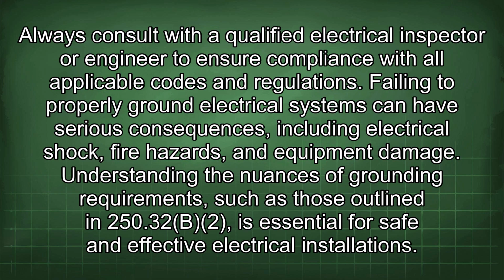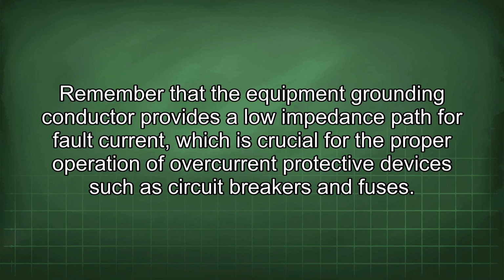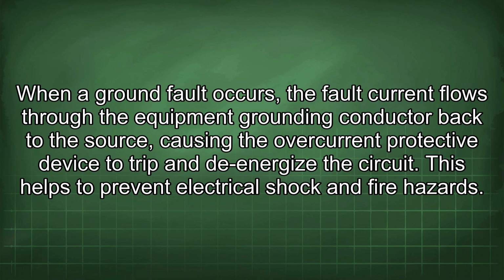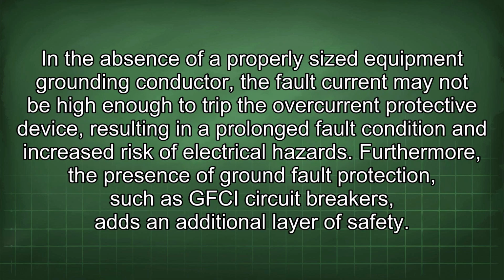Understanding the nuances of grounding requirements, such as those outlined in 250.32(B)(2), is essential for safe and effective electrical installations. Remember that the equipment grounding conductor provides a low impedance path for fault current, which is crucial for the proper operation of overcurrent protective devices such as circuit breakers and fuses. When a ground fault occurs, the fault current flows through the equipment grounding conductor back to the source, causing the overcurrent protective device to trip and de-energize the circuit. This helps to prevent electrical shock and fire hazards. In the absence of a properly sized equipment grounding conductor, the fault current may not be high enough to trip the overcurrent protective device, resulting in a prolonged fault condition and increased risk of electrical hazards.